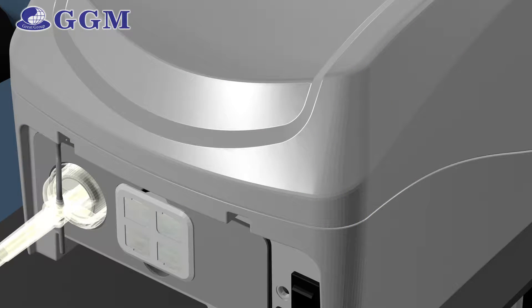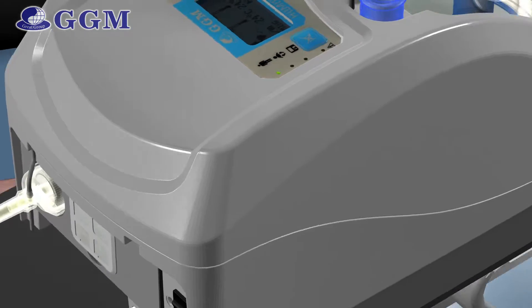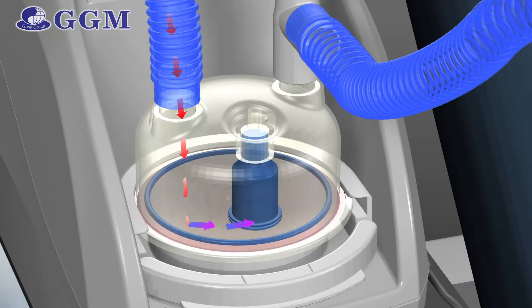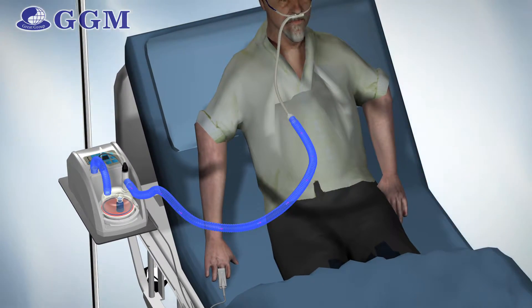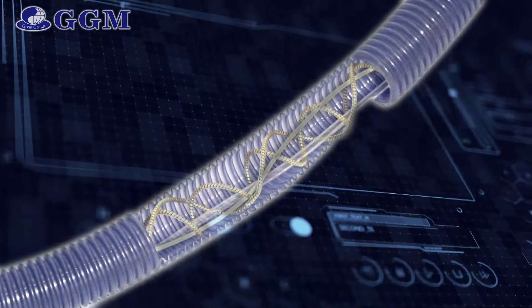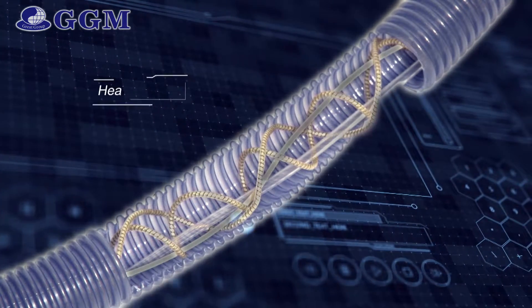Then, the blended air enters a heated water chamber, where dry air is heated to 34 degrees Celsius and humidified to optimal humidity. The heater wire in the breathing circuits warms the air to prevent condensation. Meanwhile, it brings the airway temperature to 37 degrees Celsius.